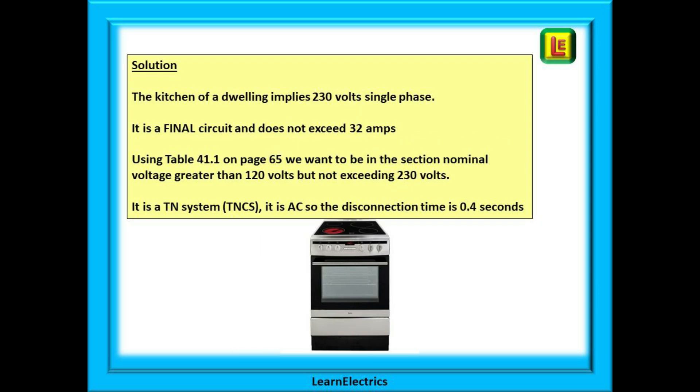We are expected to make some assumptions. In a kitchen in a dwelling implies 230 volts nominal and single phase. We are expected to make that connection. We can also assume it is a final circuit and it is not exceeding 32 amps. Looking at table 41.1 on page 65 we choose the second block. The nominal voltage is greater than 120 volts but does not exceed 230 volts. It is a TN system. It is AC and where the column and row cross is the first part of our answer, 0.4 seconds.